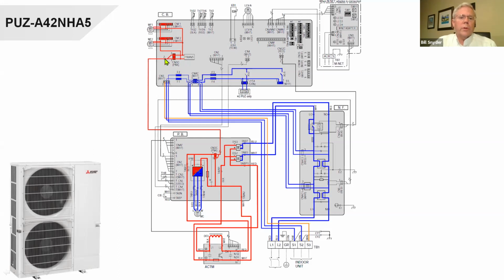You'll notice this little 2 here. This means there's 2 wires in here. And then this is 1 space and 3. That's a 3-pin connector, and we're only using pin number 1 and 3. Nothing's on 2. It's because 300 volts DC can jump. It can arc or spark. So we spread those apart on the connectors so that we don't have any arcing. Then those come up and they feed these MFs or motor fan. That's this fan and this fan on the outdoor unit.